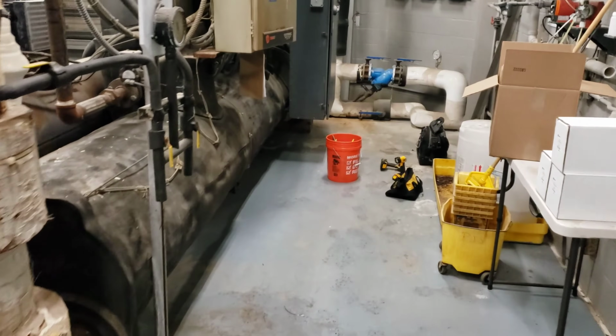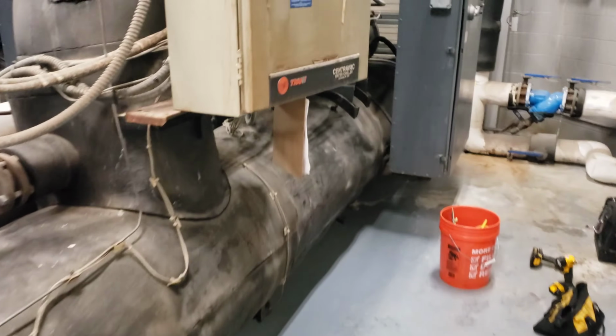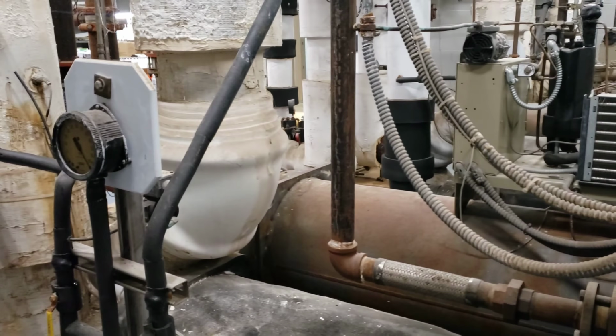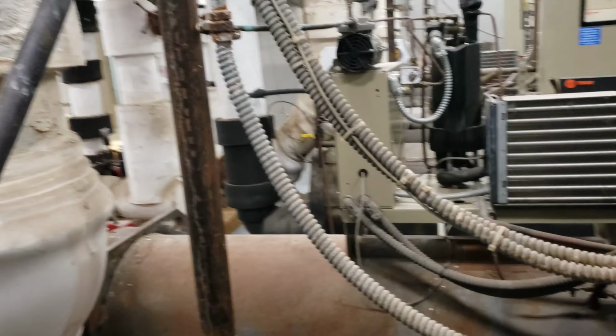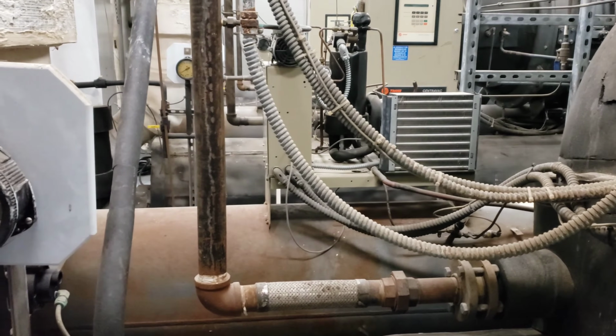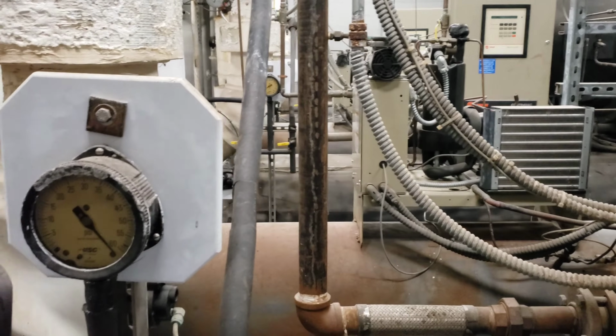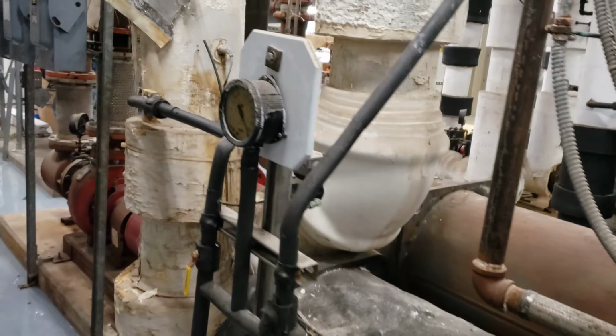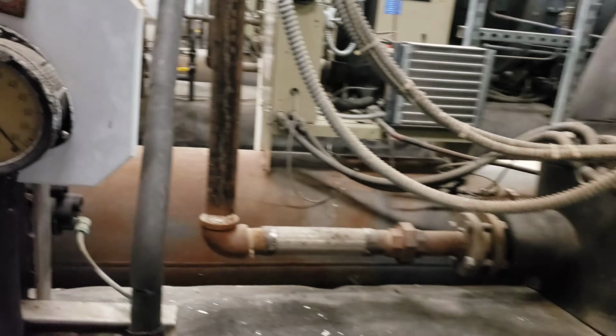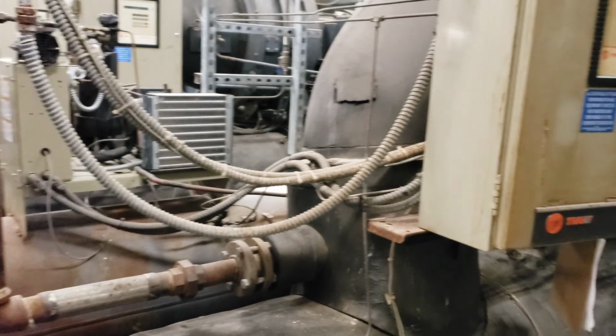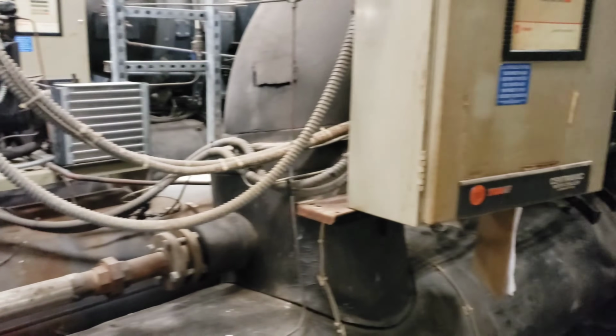Yes, this is what you sometimes run into whenever you walk into a new plant that's just full of issues, man. Like I said, I've got another plant, the building next door, a very similar setup, and it's probably in worse shape than this plant is. So I've probably got about a week's worth of work. I'm going to be doing a full PM on all the chillers, getting everything back up to snuff, getting them set to our standards as a company and to what I expect, what I try to run my chillers at, the level and the condition of them.